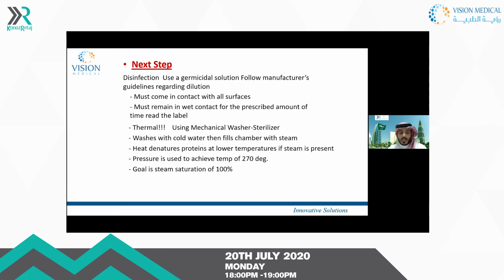Next step, disinfection. As we mentioned in the first or second slide, germicidal solution: follow the manufacturer guideline regarding dilution. It must come in contact with all surfaces and must remain in wet contact for the prescribed amount of time; read the label. Thermal, using a mechanical WD washer disinfector and sterilizer: wash with cold water, then fill the chamber with steam, which denatures protein at a lower temperature if steam is present, and pressure is used to achieve the temperature of 270 degrees. The goal is steam saturation of 100%.